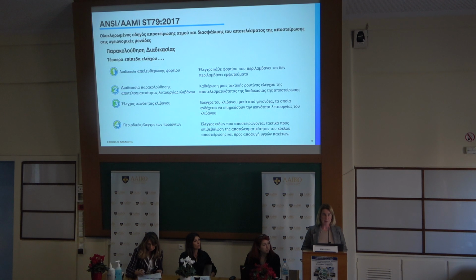I put here another example. This is called AAMI ST79. This is the comprehensive guideline which is used globally, although it is a US standard. It explains the monitoring and all about the steam sterilization processes. So from here we understand that biological indicators should be used for all loads, and especially for implants, they are needed before releasing the load. And in addition to that, for efficacy monitoring, after installation of the cycles and after maintenance, biological indicators should be used as a control.